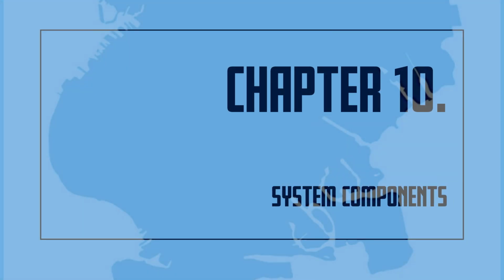10. System components. Sprinkler heads. Sprinkler heads are made of metal. They are screwed into the piping at standard intervals. The water is prevented from leaving the sprinkler head by an arrangement of levers and links. The levers and links are soldered together on the sprinkler head. The solder is a metal alloy with a fixed melting point. Other types of sprinkler heads use a glass bulb which expands and breaks under heat.